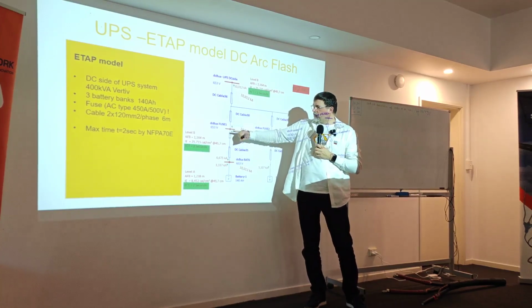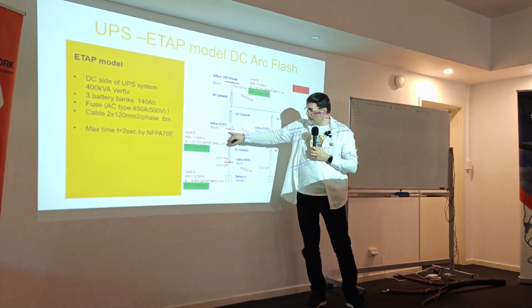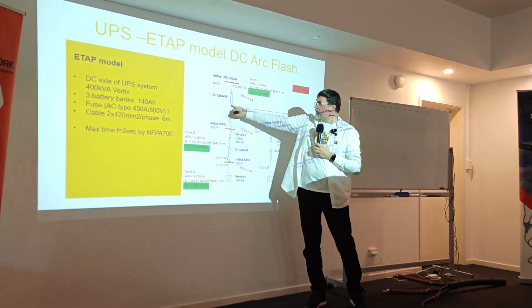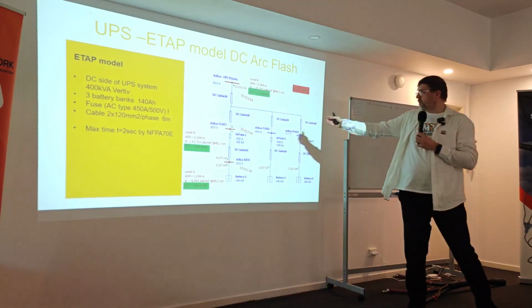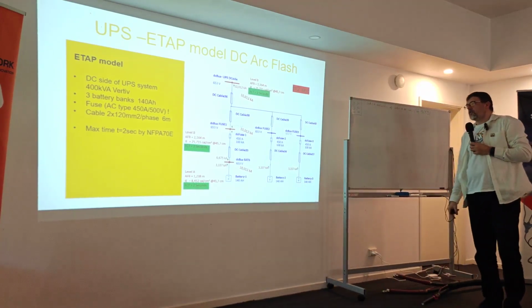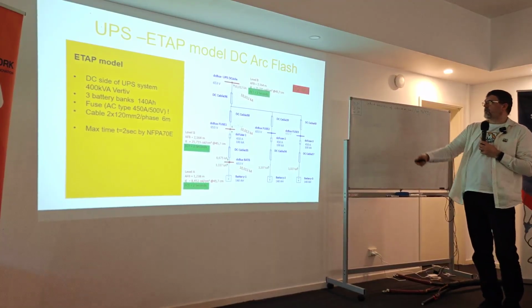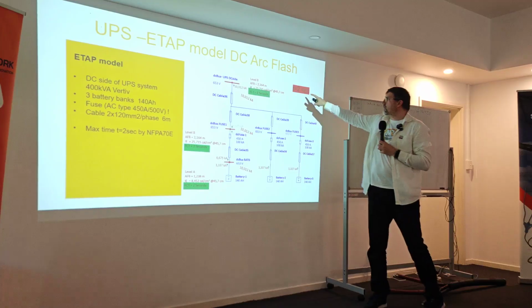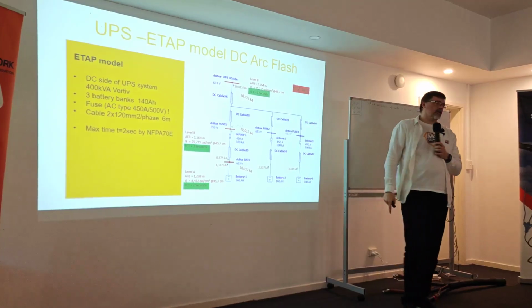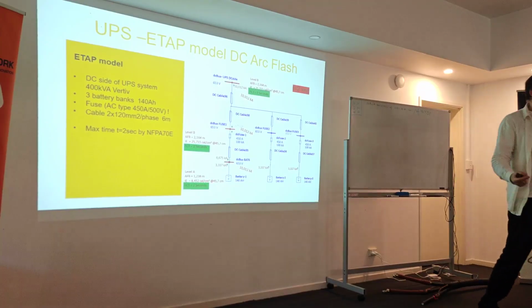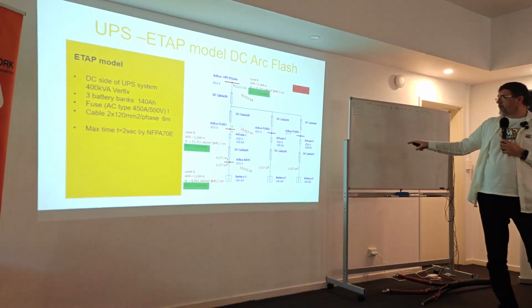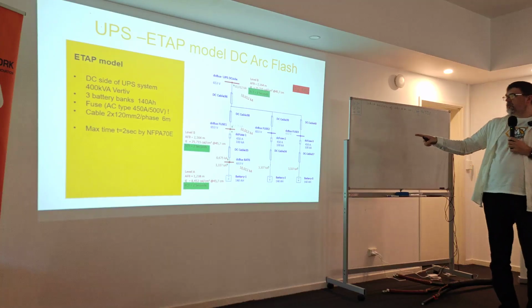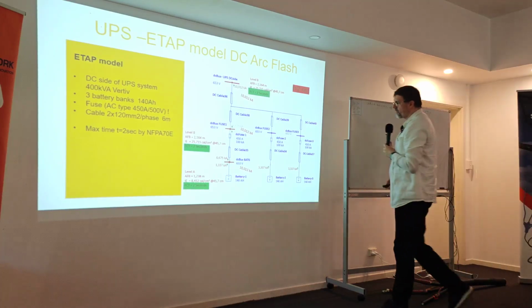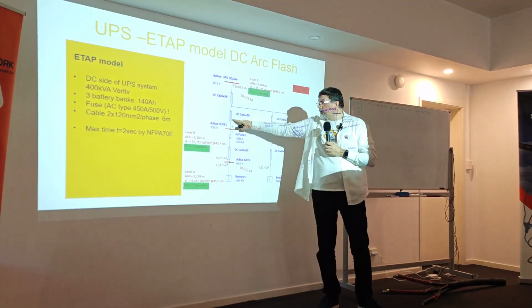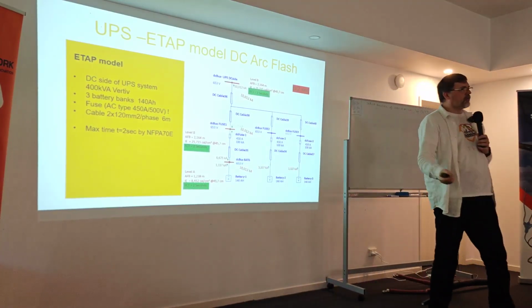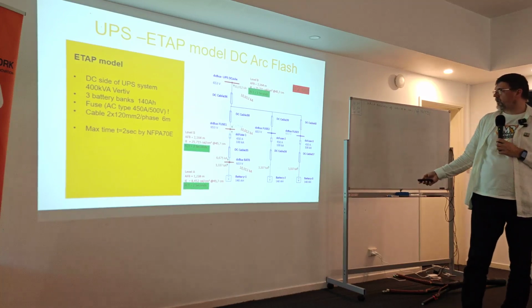Then the DC cable, the fuse, and we calculated the fuse connection because it was a panel, for the fuse, DC and common bus. And there are three strings of it. The thing behind it was that it wasn't one huge core of the inverter. Even if I kept the calculation at 2 seconds, we end up having about 25 calories at the inverter itself because of the battery short circuit current. It was mainly because of the fault and the fuse size, and then you multiply it by 3 because you have three racks.